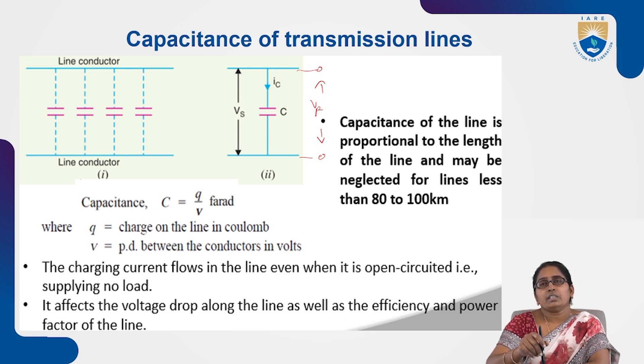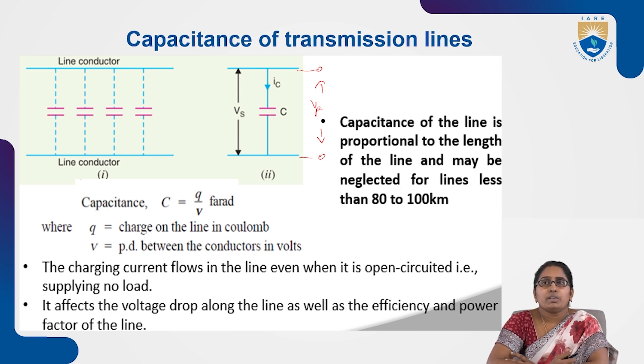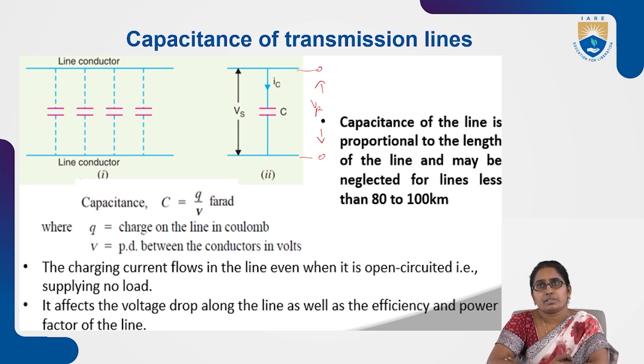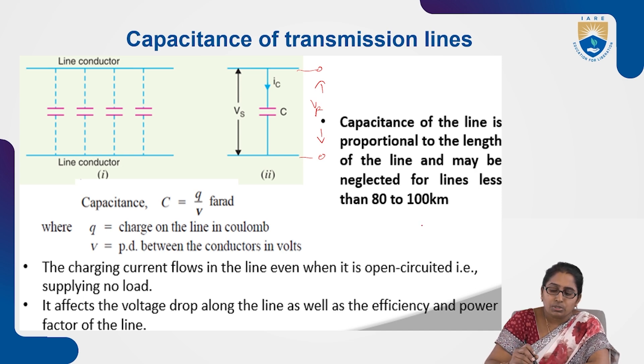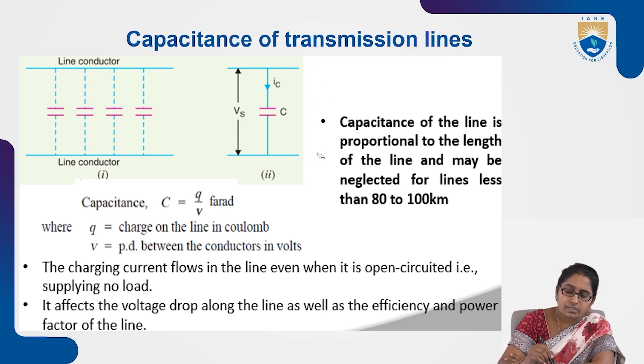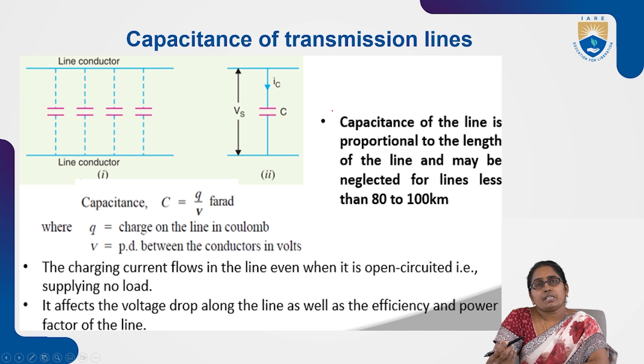Note that capacitance of the line is proportional to the length of the line. It may be neglected for a line length of 80 to 100 kilometers — the capacitance effect is not considered for transmission line lengths up to 100 kilometers. This is how capacitance is present in the transmission line and how it affects transmission line performance.